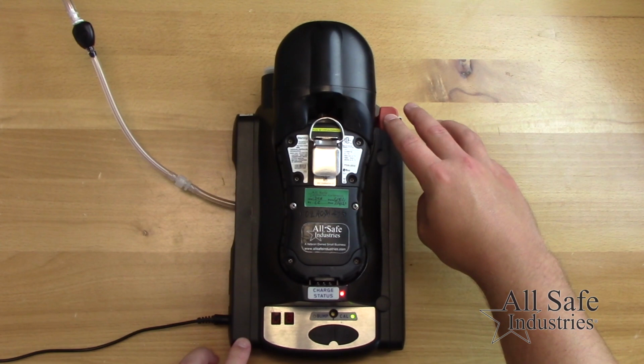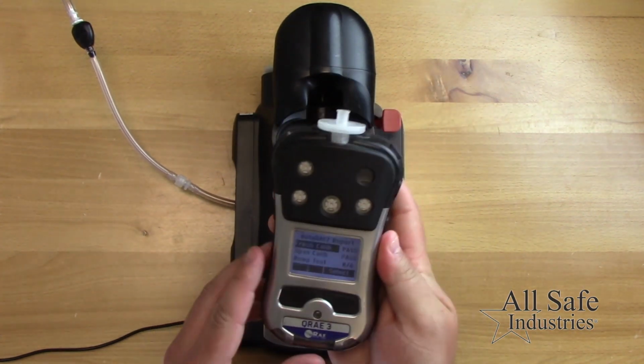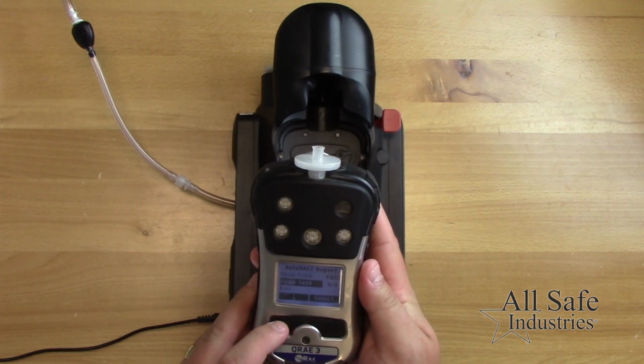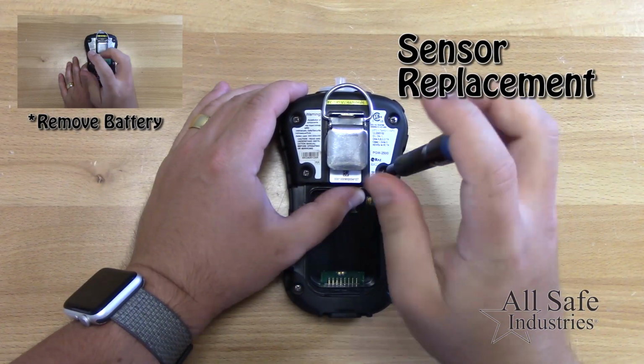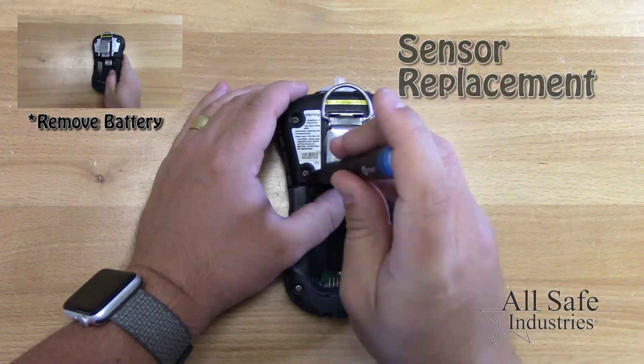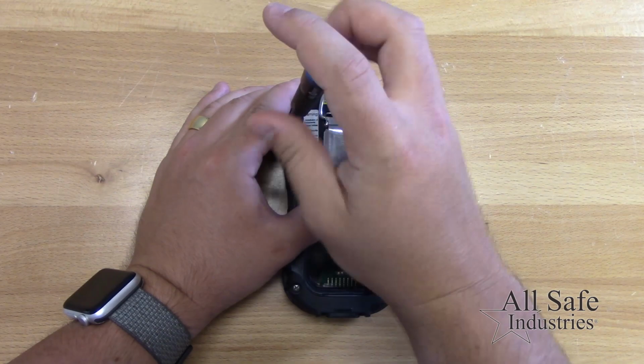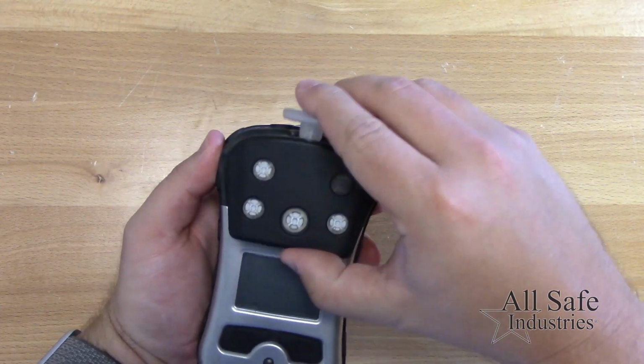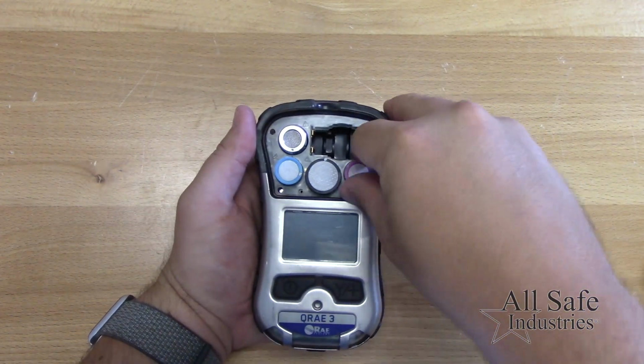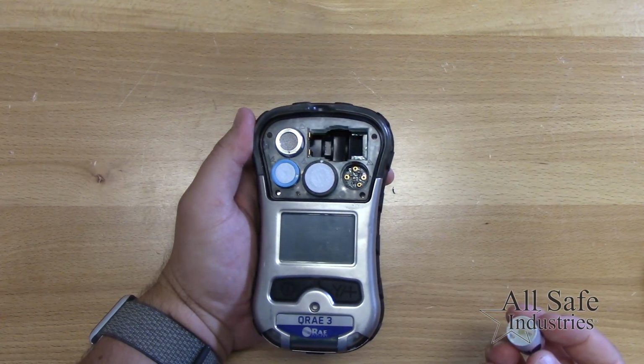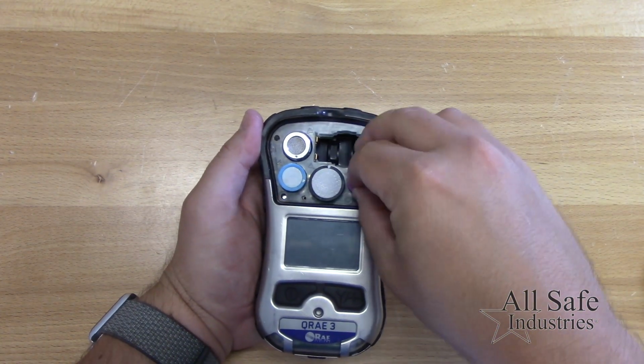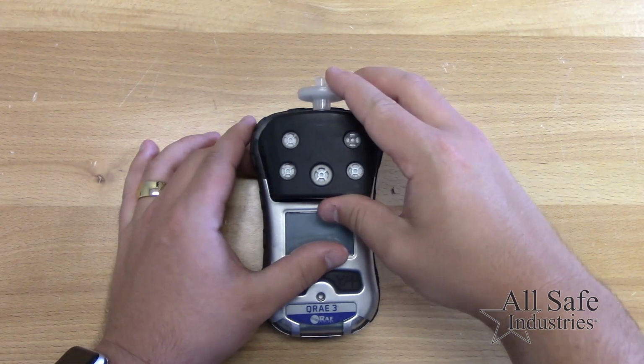Press the red trigger to release the meter from the cradle, remove the meter, and read the display for the results of the calibration. To replace a sensor that fails calibration, begin by loosening the 4 captured screws on the upper back of the meter. Flip the meter over and remove the gas plate to access the sensors. Remove and replace the sensors one at a time by aligning the pins properly.